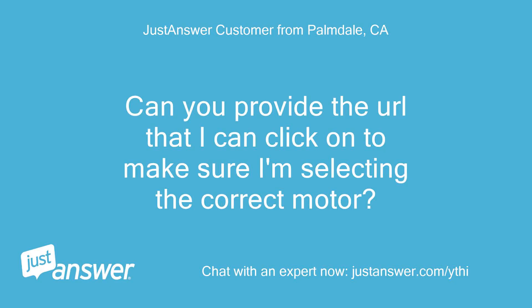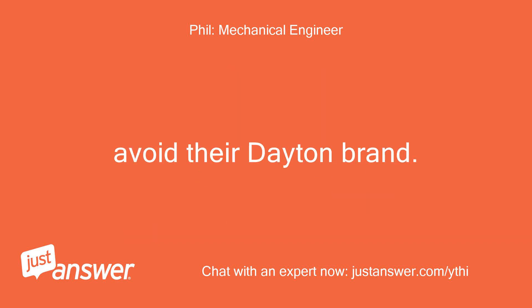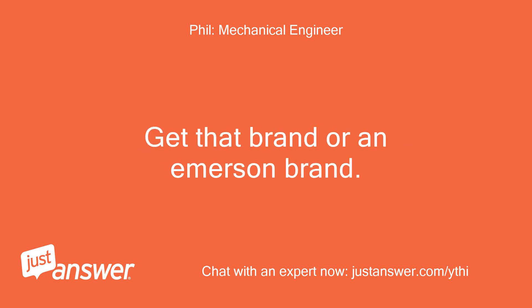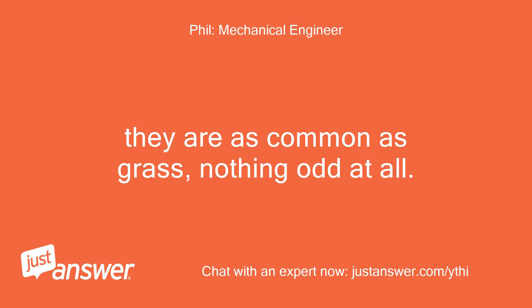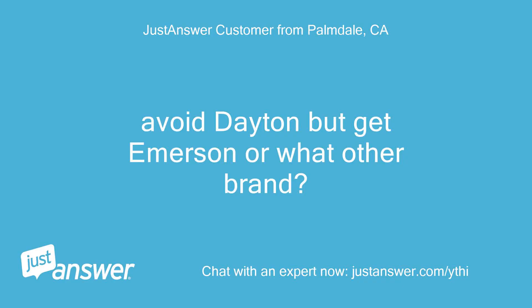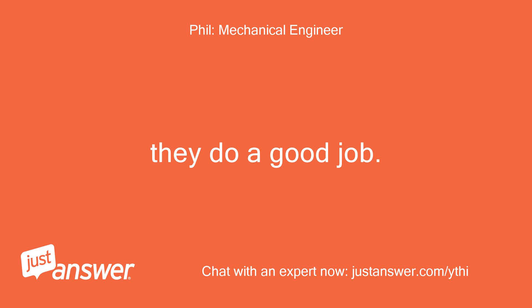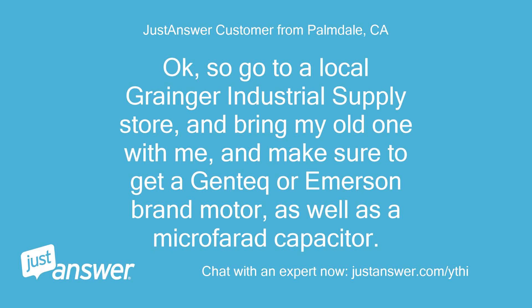Can you provide the URL so I can click on it to make sure I'm selecting the correct motor? No URL — just remove the motor and take it to Grainger Industrial Supply; the motor they give you should have identical specifications. Avoid their Dayton brand. Get Genteq brand or an Emerson brand — they are as common as grass, nothing odd at all. Get a new 7.5 microfarad capacitor to go with it. So go to a local Grainger Industrial Supply store, bring my old one with me, and make sure to get a Genteq or Emerson brand motor, as well as a 7.5 microfarad capacitor.